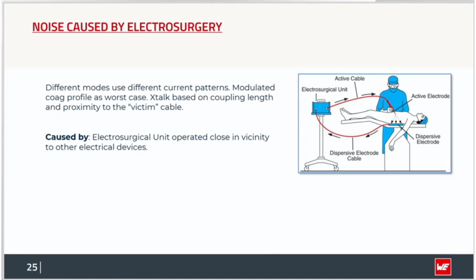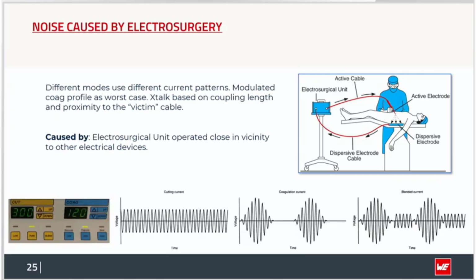And this can also be used during endoscopy, where the active electrode is operated remotely. There are different profiles of current used in this procedure. There's a cutting current with a continuous waveform, and there's a coagulation current with a modulated waveform. The frequencies are usually a couple of hundred kilohertz up to 2 megahertz. That's well above the frequency where neuromuscular activity is induced. And there's also blended current, which is a mixture of these modulations.